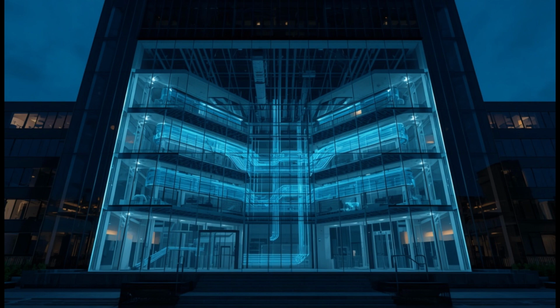Here and there along the branch ducts, a small manual damper interrupts the smooth metal, a simple adjustable blade set into the duct at a fixed angle and locked into place with a single bolt. These are balancing dampers, and their purpose has nothing to do with the moment-to-moment adjustments made elsewhere in the system. Instead, they were set once, carefully, by a technician working through the building shortly after construction, walking from branch to branch with a measuring instrument in hand, adjusting each damper by hand until every corner of the building received its fair and proper share of the air the fan was providing.